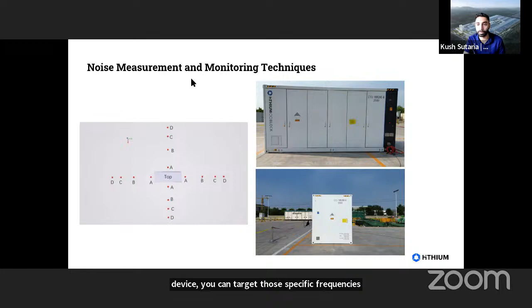We generally record for 30 seconds and repeat for each different location, for each different fan and compressor speed, so we can give you sound data across the whole range of container powers that you can put into your model. And as Darrell mentioned, we not only give you the overall dBA per location, but also break it down into frequency octave bands, so you can find out which frequencies are dominant and target those specific frequencies, rather than applying a broad brush sound mitigation device.